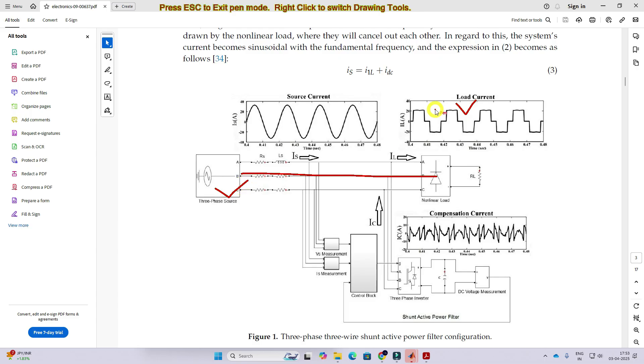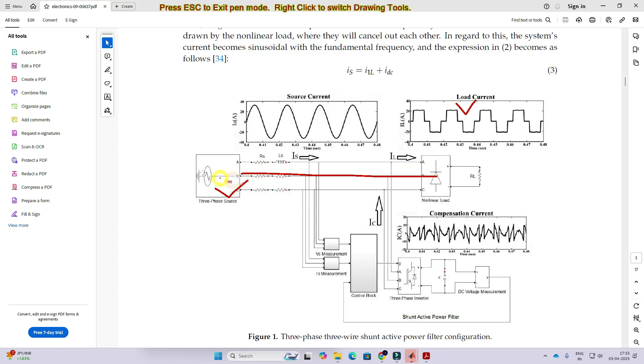This load current and source current both have similar non-sinusoidal nature. It draws some reactive power from the three-phase source and affects the sinusoidal nature of the grid or source current. The THD will be increased more than five percent. So we need to maintain that source current always sinusoidal, and for that purpose we use the shunt active power filter.